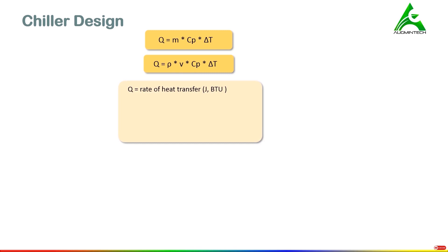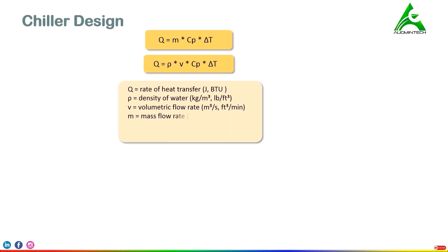Here are the details of each term used in the equation. Q is rate of heat transfer, measured in joules or British thermal unit. Rho is the density of water — in SI we use kg per meter cube, and in IP system we use pounds per feet cube. V is volumetric flow rate measured in meter cube per second or cubic feet per minute (CFM). M is mass flow rate, measured in kg per second or pounds per minute.